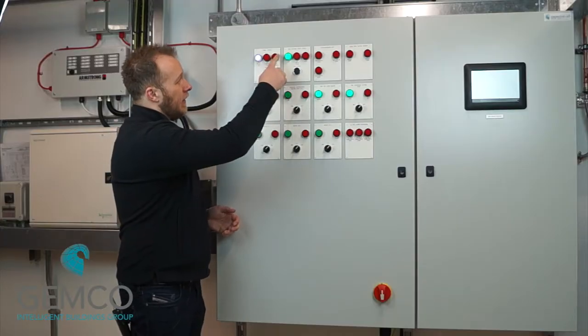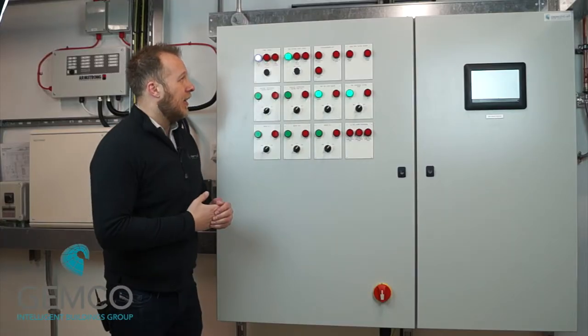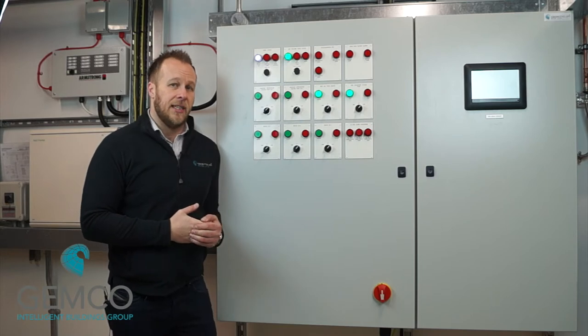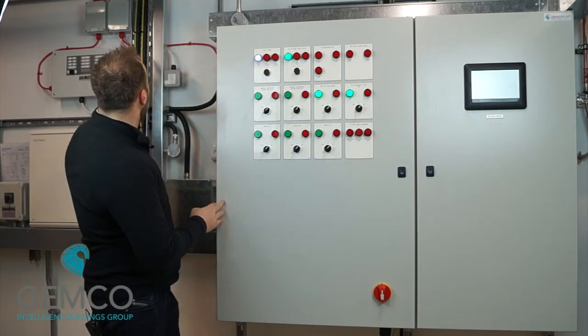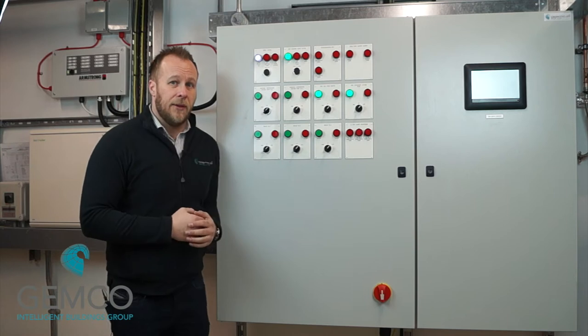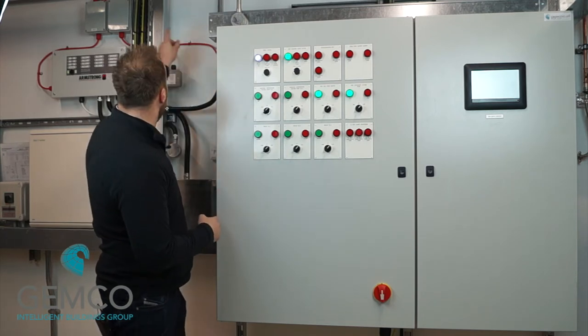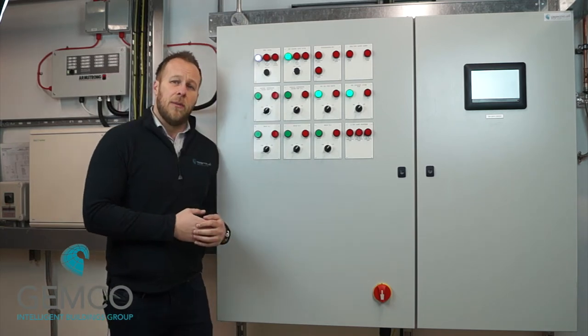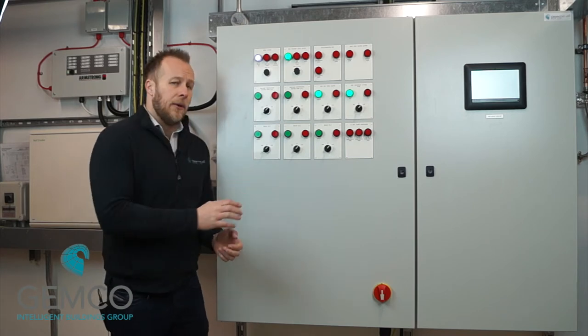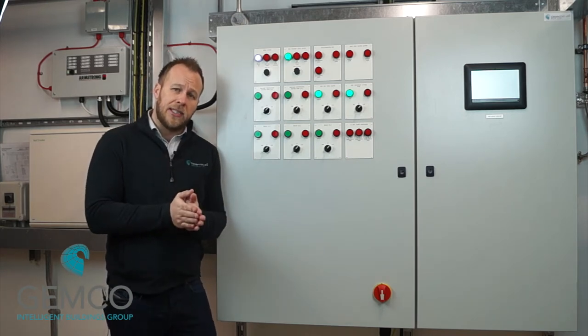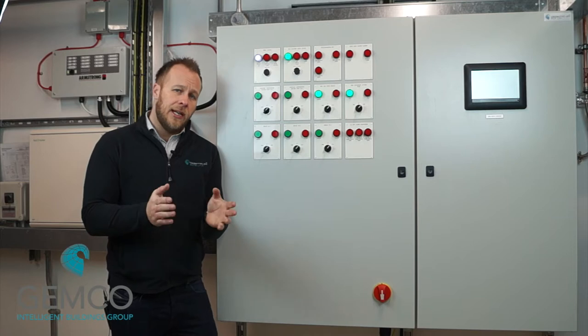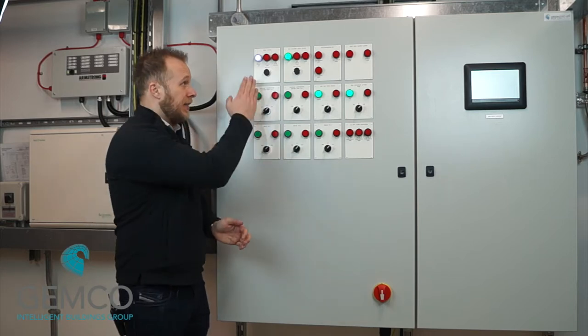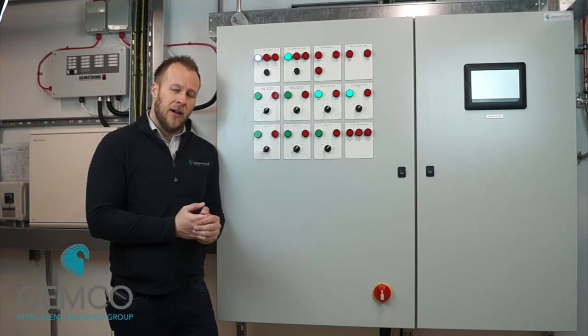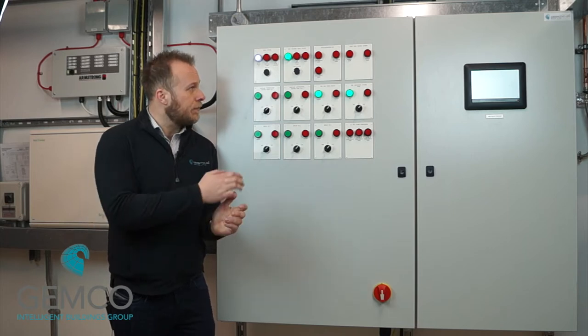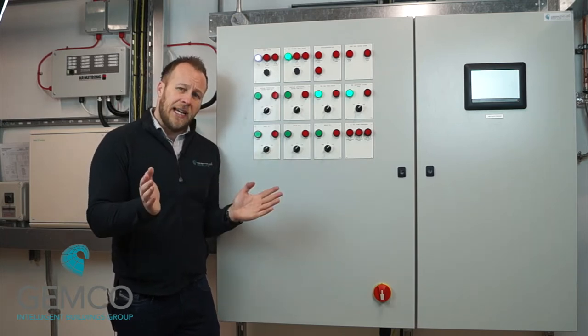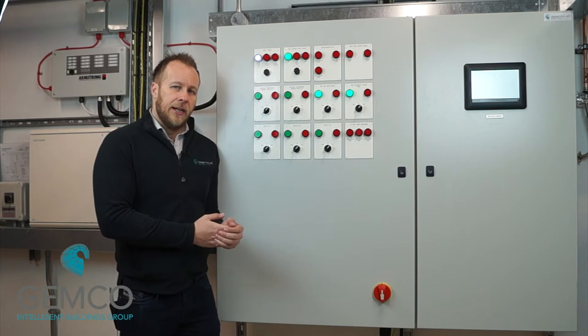And the last lamp on the label is the fire alarm detected. So there's a fire interface just above the panel there, where this red cable goes into. That is the fire alarm relay box, and this control panel just monitors a volt-free contact in that fire alarm relay box. It's a normally closed contact. It's wired into the first two terminals on the left-hand side in the panel, and if that circuit breaks, that'll also shut the plant down.